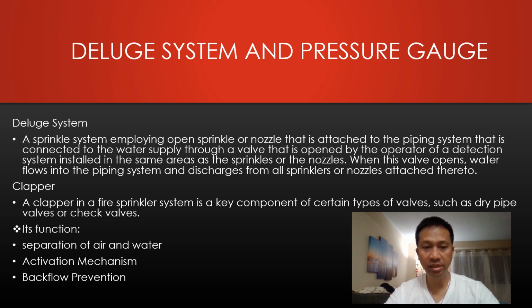Oh, it's a clapper, sorry, not a pressure gauge. A clapper in a fire sprinkler system is the key component of certain types of valves, such as dry pipe valves or check valves. Its functions are separation of air and water, activating the mechanism, and backflow prevention.